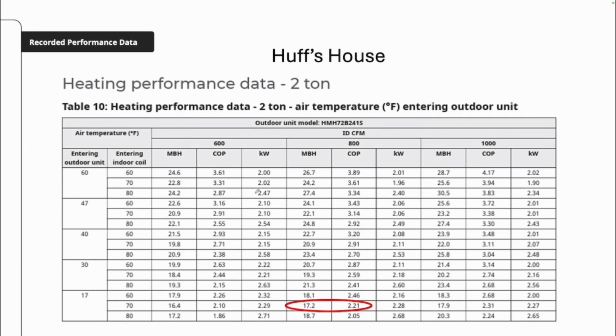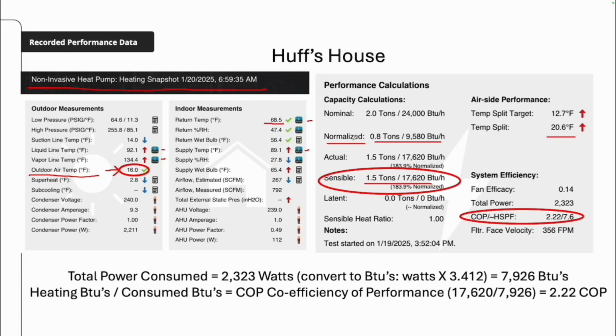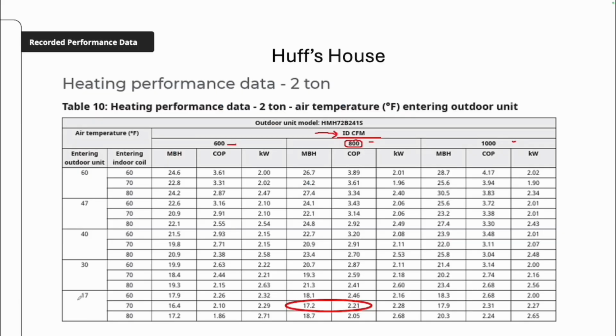Now, I'm going to show you what the actual data from York says my system should be doing. This is a York side discharge inverter heat pump, and we're going to look and see what the data says I should be delivering. At the top we have indoor CFM, and we've got 600, 800, and 1,000. My CFM was actually 892, if I remember correctly. Let me go ahead and double check that. 792. Yep, 792. And right here we have the capacity at 17 degrees outside, at 70 degree entering dry bulb air.